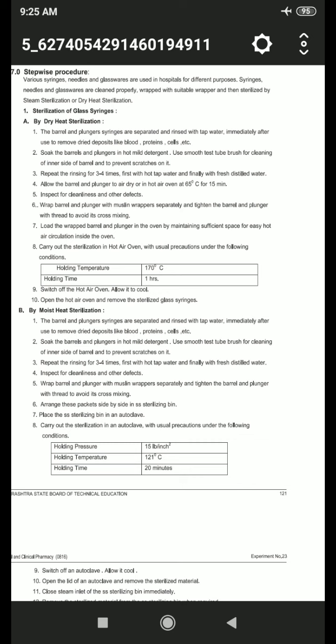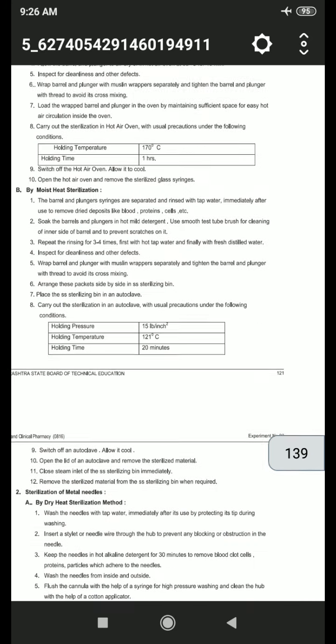Okay, then the next step is to arrange these packets side by side in an SS sterilizing bin. Then place the SS sterilizing bin in an autoclave. Then carry out the sterilization in an autoclave with usual precautions under the following condition. First, holding pressure is 15 lb per inch square. Then holding temperature is 121 degrees Celsius and holding time is 20 minutes. In dry heat sterilization, holding temperature is 170 degrees Celsius, and in moist heat sterilization, holding temperature is 121 degrees Celsius. Holding time for dry heat sterilization is 1 hour and for moist heat sterilization 20 minutes, and holding pressure in moist heat sterilization is 15 lb per inch square.